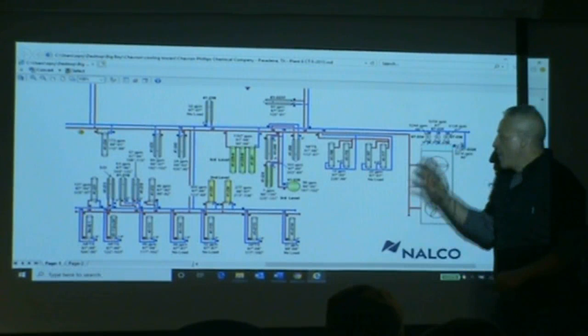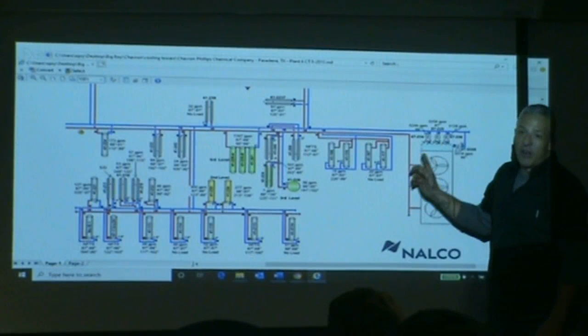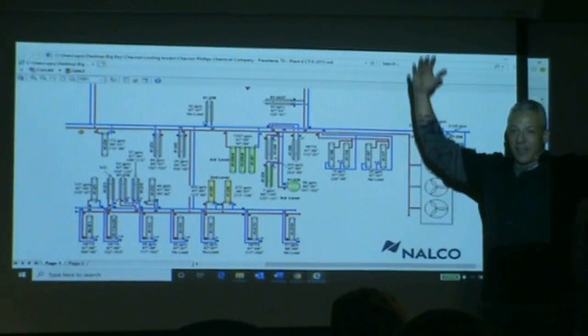Sidebar: I told you these pipes are this big around, made out of metal, carbon steel. What's the one thing you have to make sure of with this water to protect that pipe? pH. You let the pH drop down to a 4 for a little while, and it'll eat 36-inch piping to death.